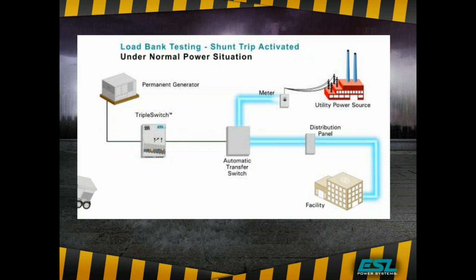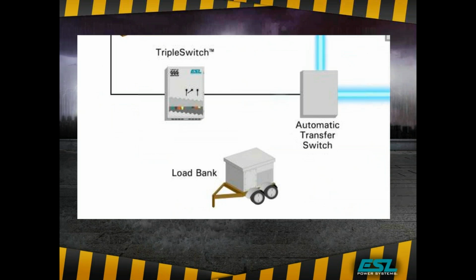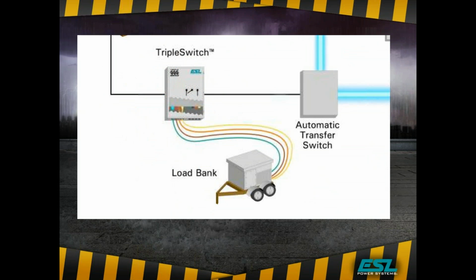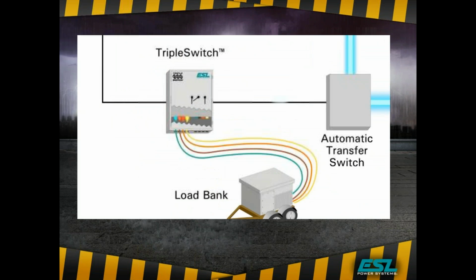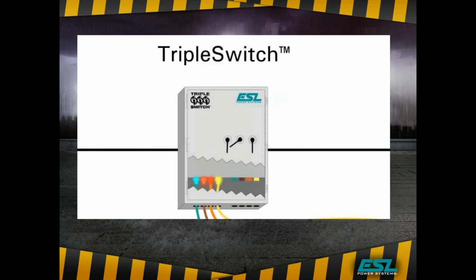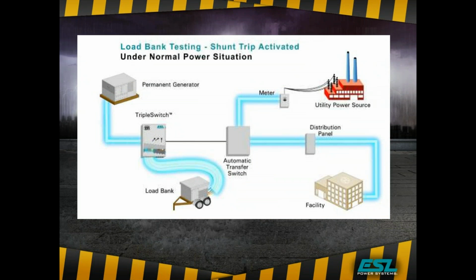When load bank testing of the permanent generator is required, under normal conditions, a load bank tester is connected to the load bank connection point in the triple switch. The center breaker is left on. Next, the left-hand breaker is turned on. This connects the permanent generator to the load bank connection and also leaves it connected to the ATS. The permanent generator can be started and the load bank testing can be done.